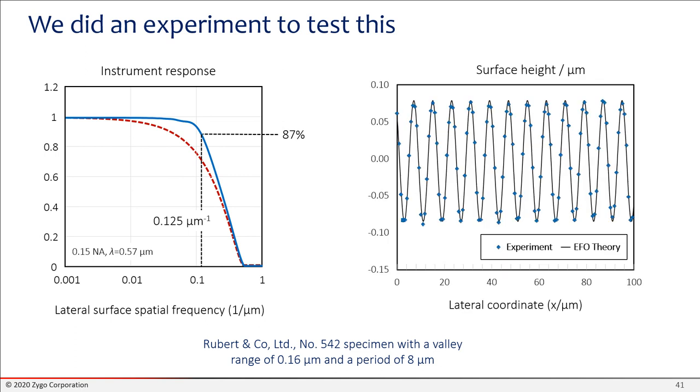So we did an experiment to verify this. We found a sinusoidal sample at close to 0.1 inverse microns, at 0.125 inverse microns, and we did the measurement. And what we found was that indeed, the experiment matches the theory very well, and that the attenuation at this spatial frequency is about 13%, not the 25% or 26% that we would have expected if we were following the MTF. So that gives us some confidence that we are accurately predicting the response of the instrument.